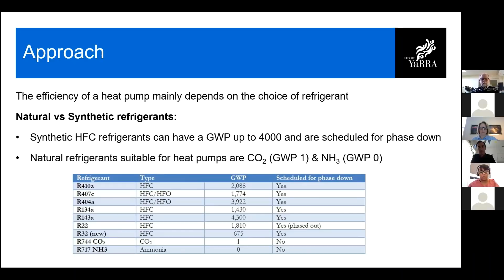What we found out is that they are generally small in capacity. So for the massive heat demands of an aquatic center, we would need a bank of 5-10 pumps or even more, or you would need to use a gas backup during big demand days or seasons. They have an average COP of 4.2, which is reasonable. But the reason we decided to rule them out, and decided that they are not the most suitable for an aquatic application, is that carbon dioxide as a refrigerant has a critical temperature of 31 degrees.